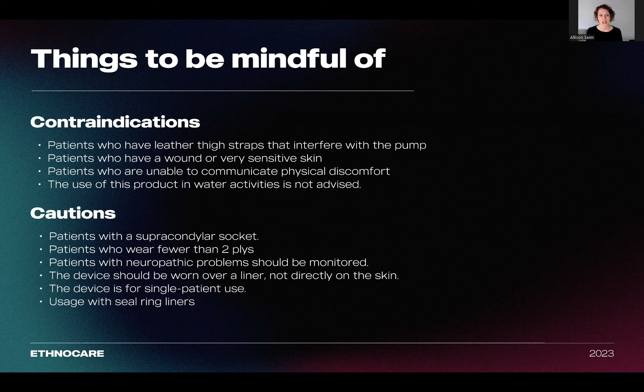We also recommend being cautious about using this product for patients with a supracondylar socket. Of course, we know many patients use this type of socket design, but that said, as you know, the ears of the socket go much higher with this socket design and could, in some cases, interfere with the pump and the valve. Patients who wear fewer than 2 plies, since this product corresponds to a thickness of approximately 2 ply. Any patients with neuropathic problems should be monitored when using this product. This device is worn over a liner and not directly on the skin. This device is also intended for single patient use.